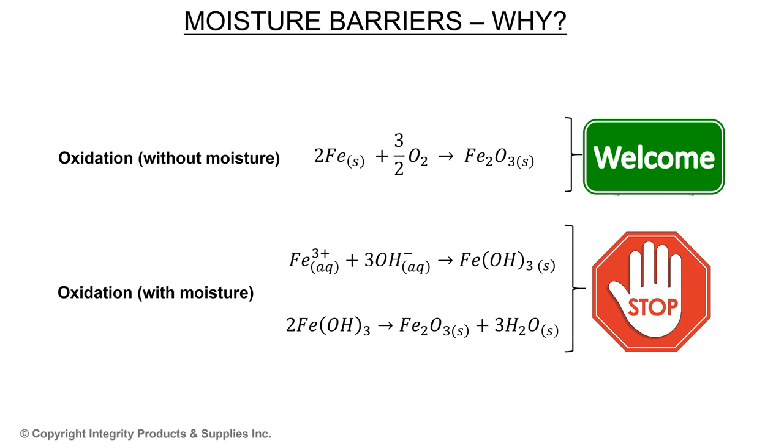And when we talk about moisture activity, what does moisture do? The hydroxyl ions from the moisture or the water droplets interact with the iron and form iron hydroxide, which then gets decomposed into the oxide scale. The moisture again contains dissolved iron ions, and again it triggers the oxide scale formation, and the oxide scale again gets damaged because of thermal cycling or incoming moisture. So this way this reaction continues. And the moisture presence we have to avoid. We have to eliminate the moisture from the system so we can control this second reaction of consistent oxide scale formation and breakage.